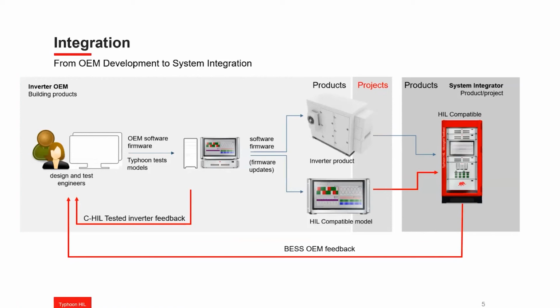Now the system integrator can add this library component to their system model alongside the HIL-compatible device hardware and run all the integration tests they need. This test may include other HIL-compatible devices, such as other inverters, genset controllers, relays, microgrid controllers, and so on. If they find any issues on either the model or the performance of the product, they can give this feedback to the OEM, which would improve the model firmware, run the automated test verification and validation process again, and distribute this updated model and firmware to all their customers.